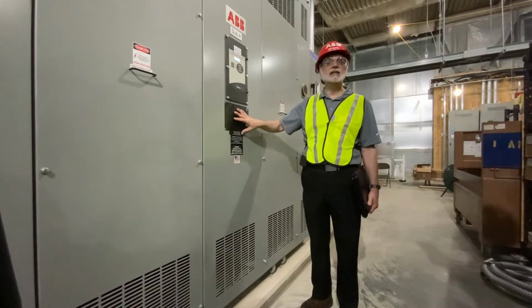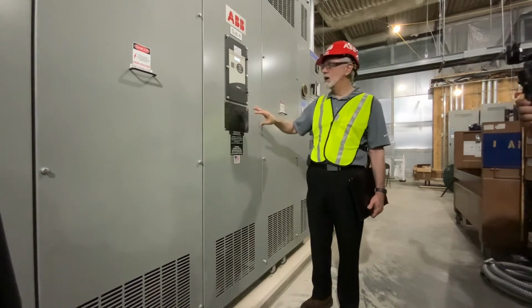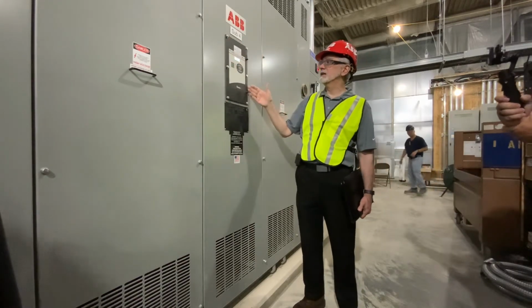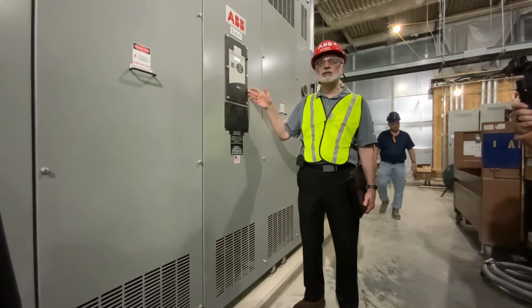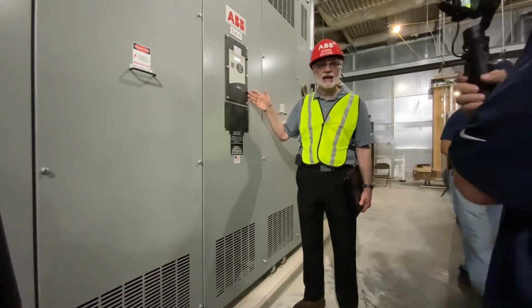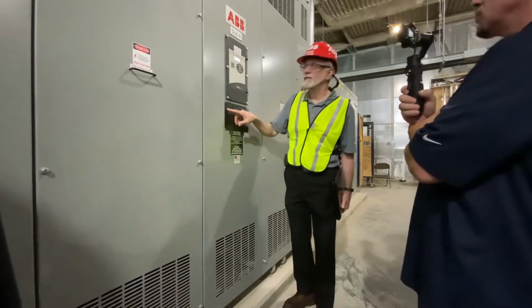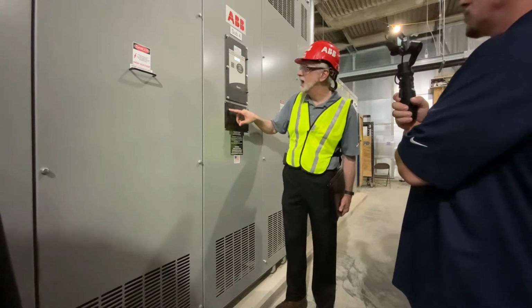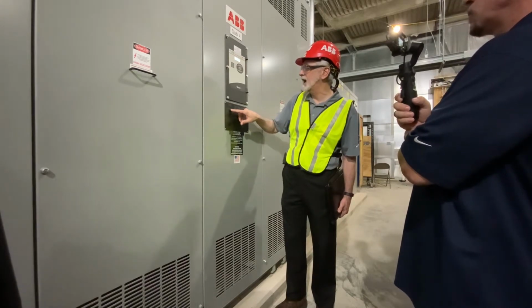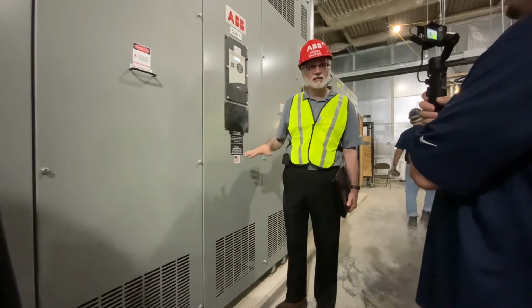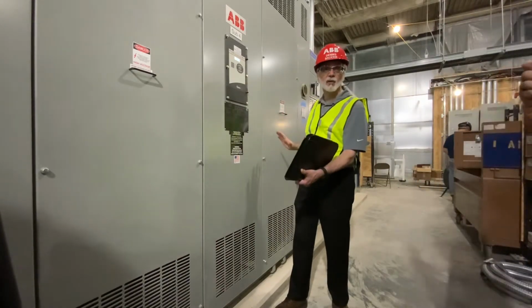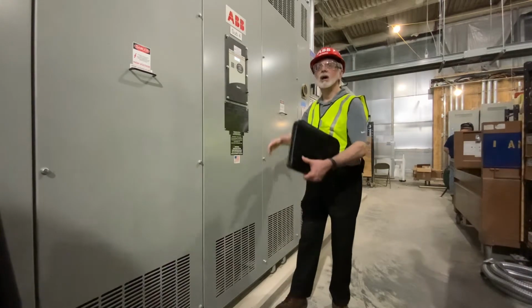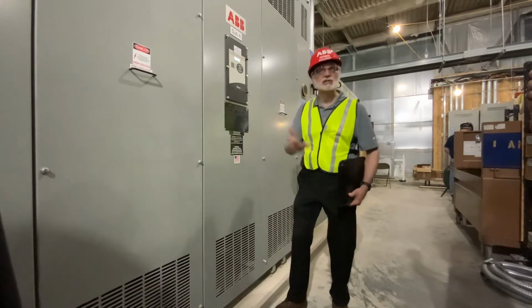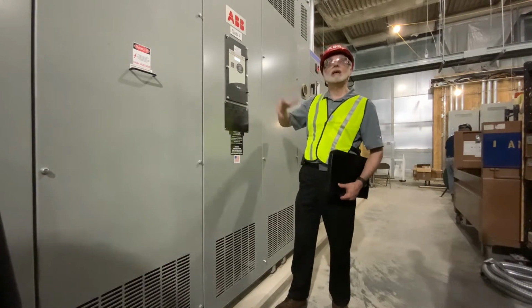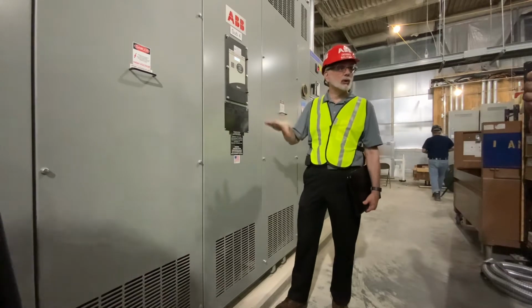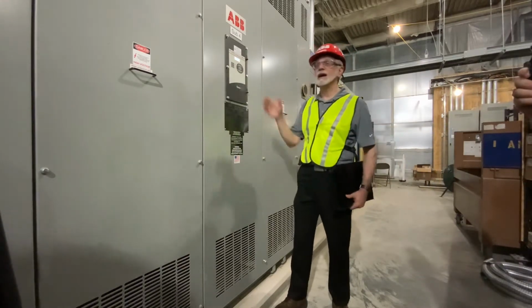This particular transformer has an ambient rating, and it's also got a forced air rating. So that's what this compartment is here. This is a transformer temperature monitor, but it also has the ability to kick in fans. This transformer has a rating of 1500 kVA, but it can also go up to 1995 or 2000 kVA with the fans on. So we're not really changing the transformer itself. The transformer is the transformer, but when we force air through it as opposed to just normal ambient air convection, we can get more power out of it because we make it run cooler by putting fans on it. So that's the reason here.